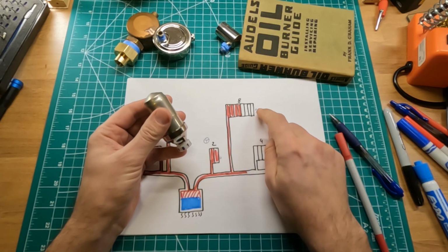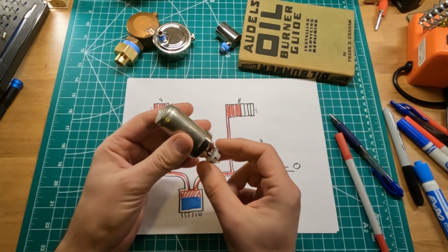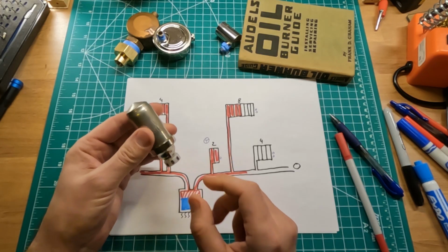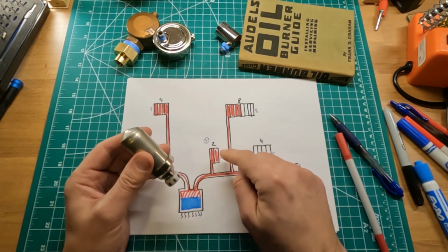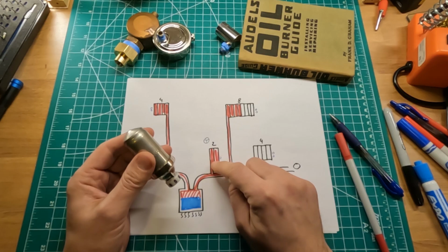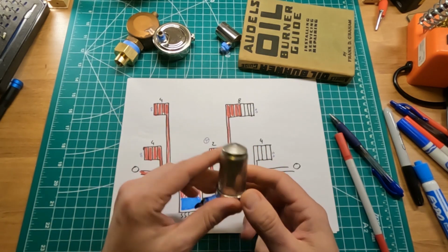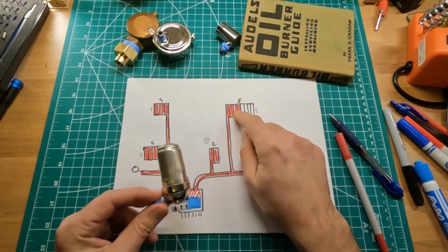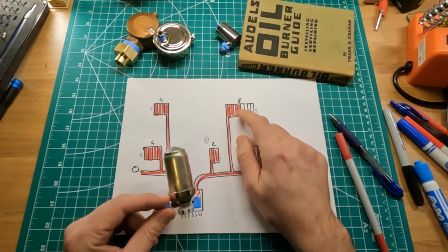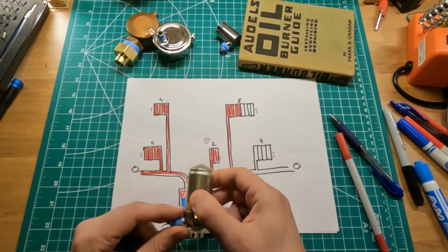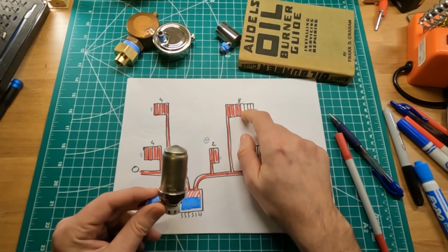So there are double circles, really meaning opening up all the way, while this radiator is just halfway down. So to double the air venting rate of this radiator, you have to open up all the way. And then when you open up totally, you're in a pickle, because this radiator, at least in our practice here, will never heat up properly.